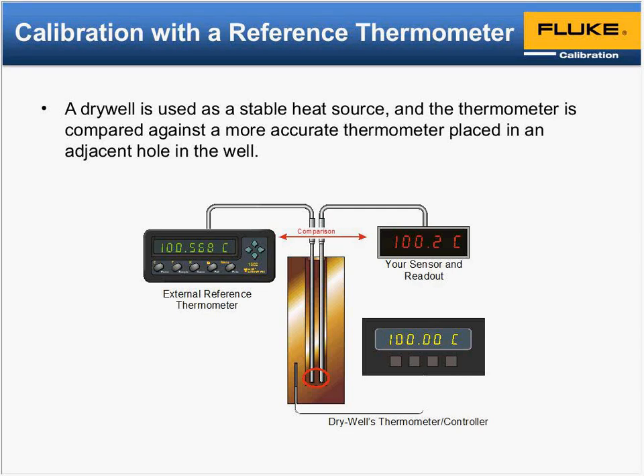In an auditing situation, that's why we offer these, and that's mainly for folks that want the robustness of component calibrations, but also want to satisfy their auditors. Again, we've touched on a few times here, sometimes the uncertainties can be difficult. So again, with system calibration, the unit is 0.2 degrees C. I don't know if the 0.2 is coming from the probe or the readout or a little bit of both. Again, there's that aspect. They do lack a little bit of robustness in that regard, again, too, compared to components. Again, that's due to the compensation and readout error all being adjusted in a single piece, the electronics in the readout. So again, something to think about as far as what's right for you.